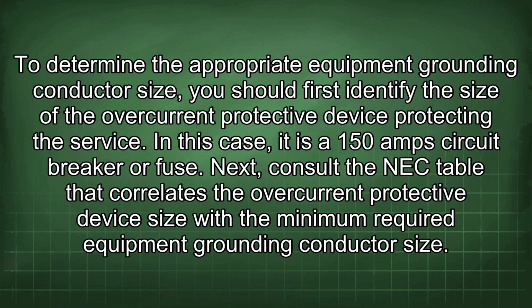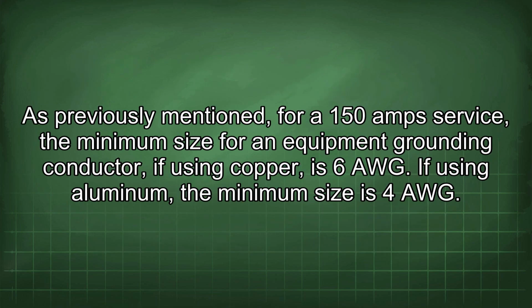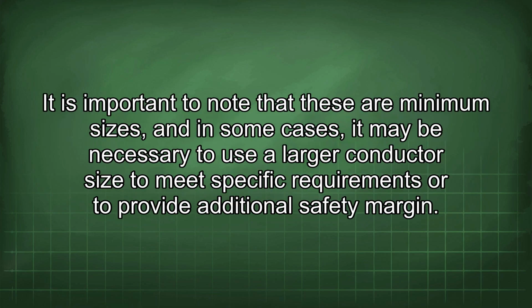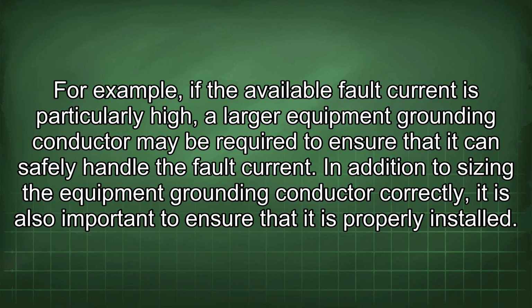To determine the appropriate equipment grounding conductor size, you should first identify the size of the overcurrent protective device protecting the service. In this case, it is a 150 amp circuit breaker or fuse. Next, consult the NEC table that correlates the overcurrent protective device size with the minimum required equipment grounding conductor size. As previously mentioned, for a 150 amp service, the minimum size for an equipment grounding conductor, if using copper, is 6 AWG. If using aluminum, the minimum size is 4 AWG. It is important to note that these are minimum sizes, and in some cases, it may be necessary to use a larger conductor size to meet specific requirements or to provide additional safety margin. For example, if the available fault current is particularly high, a larger equipment grounding conductor may be required to ensure that it can safely handle the fault current.